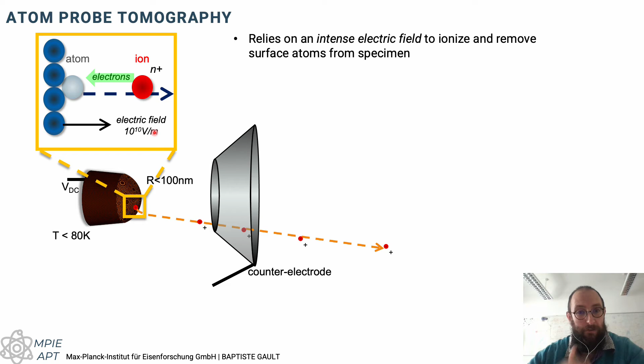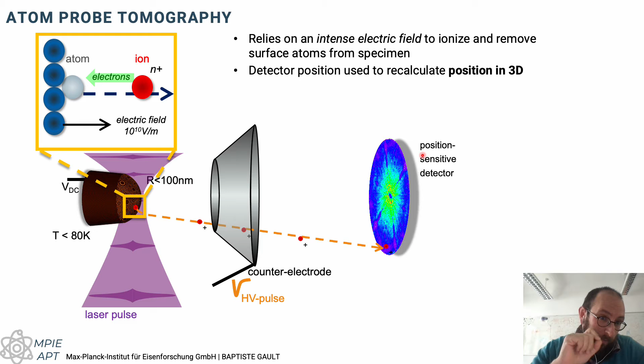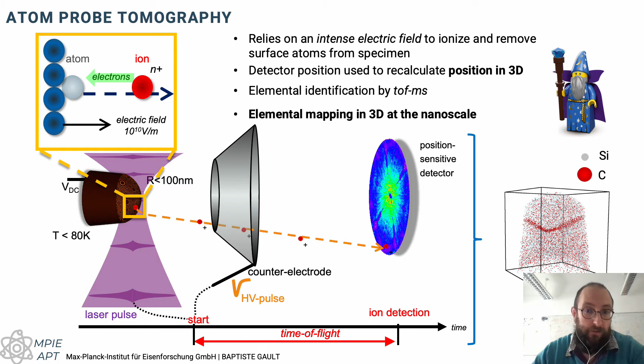We collect these onto a detector that is sensitive to the impact position. We time the departure of the ions by using either high voltage pulses that will temporarily increase the amplitude of the electrostatic field, or by using laser pulses that will temporarily increase the temperature of the specimen apex. And this gives us the start of the time of flight measurement, and we can measure the time of flight up until the point where the ion strikes the detector. This gives us a means to use time of flight mass spectrometry to identify each ion, so we can associate to each ion an elemental identity. The impact position and the order in which we detect the ions can be used to build a 3-dimensional point cloud where each point is one ion that was detected and repositioned in 3 dimensions.